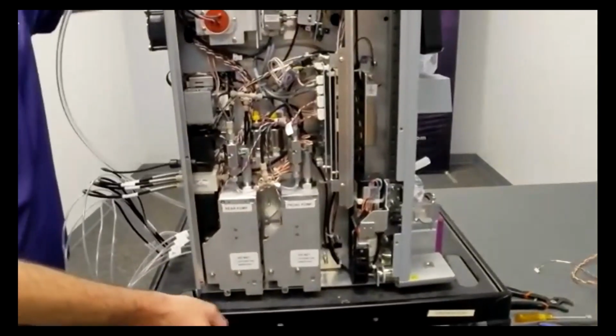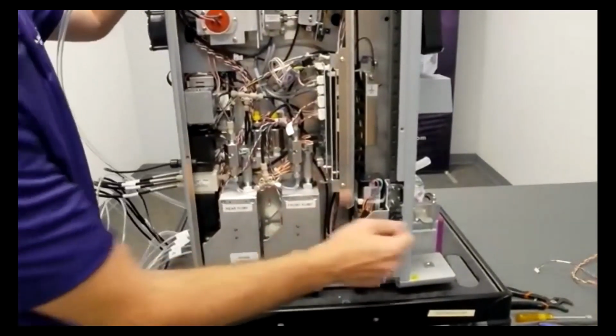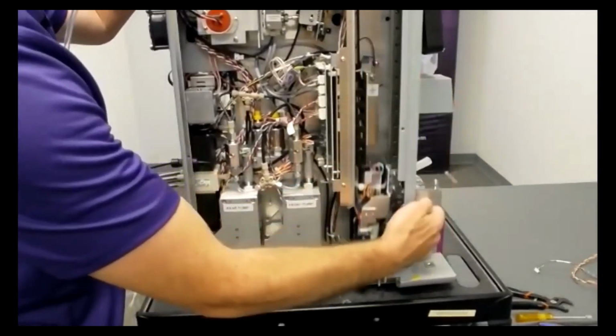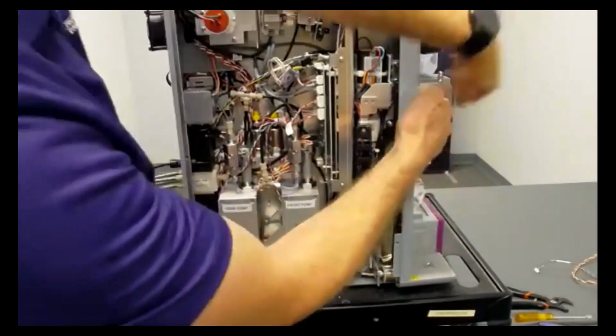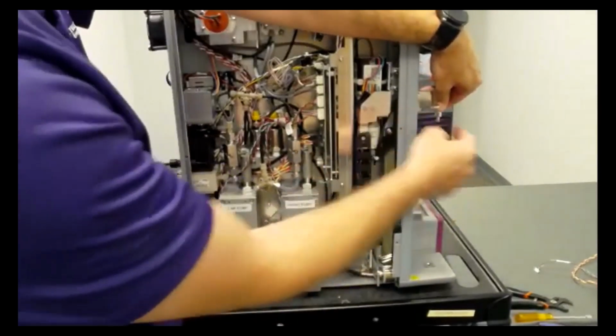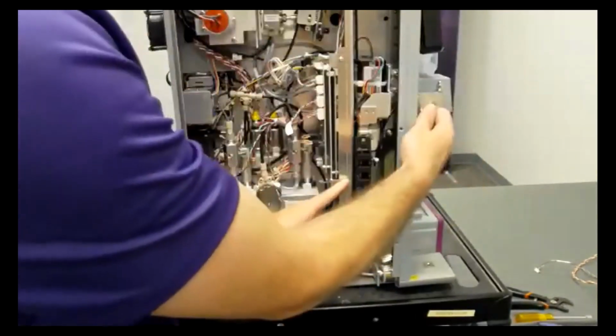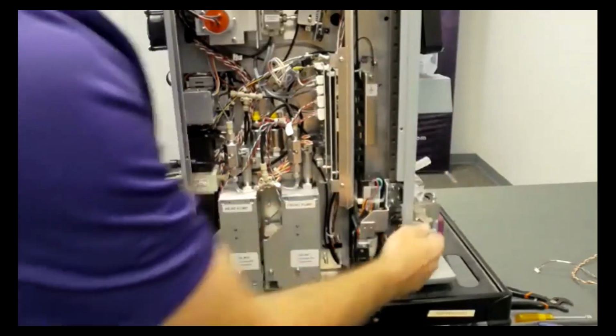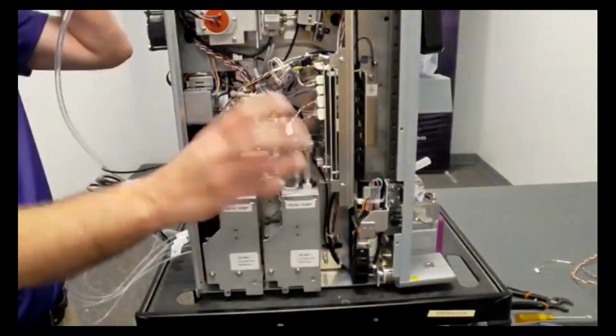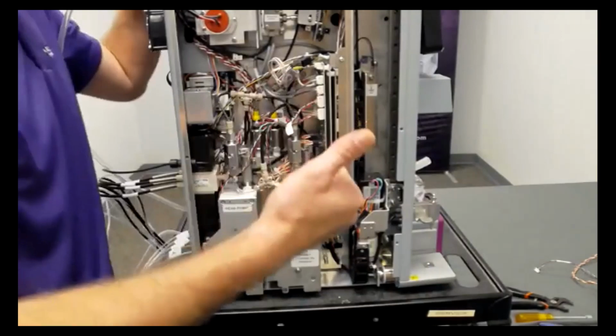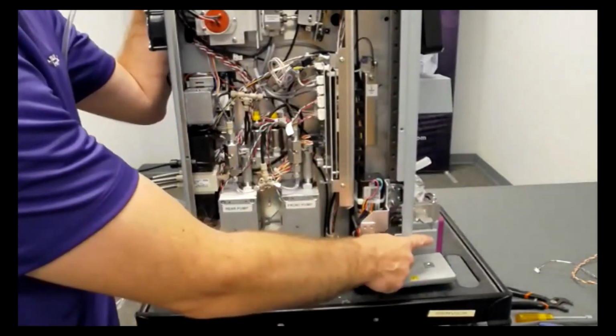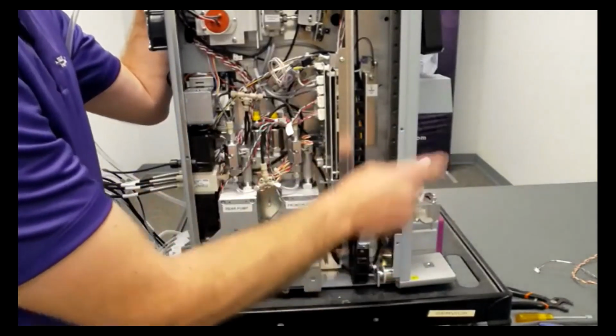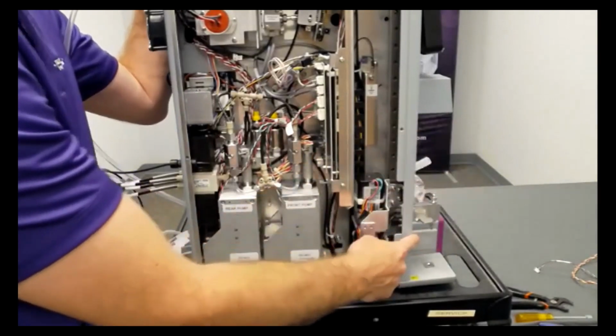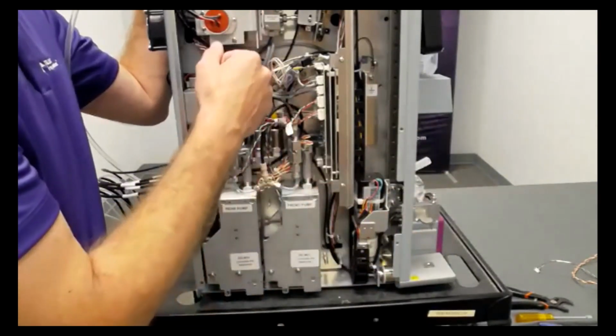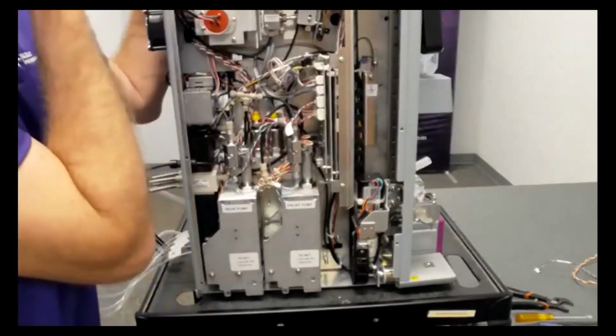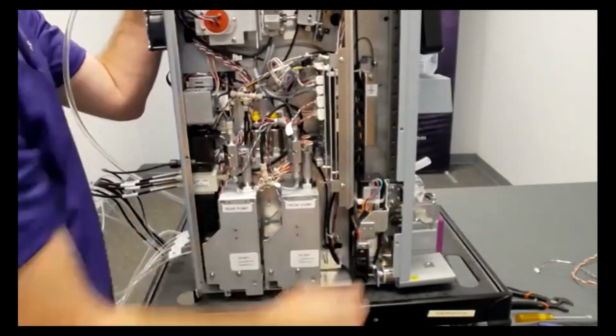So here in the bottom, I've got my injection valve. All right, this moves up and down with the trolley. So when you install a column down here, you have to move the trolley up, and the injection valve will move with it. The injection valve just changes your flow path with a rotor. So you can go direct to waste, you can go through the column, but not the cartridge. You can go through the cartridge and the column. You can go direct to the flow cell, things like that, okay? So that's what the injection valve does.